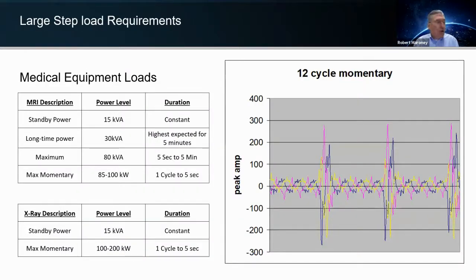So another type of load or requirement for a lot of people, and that is getting into medical equipment loads, is high nominal to peak requirements. Remember that 14 times inrush current we can provide? When you put a rotary UPS in, this capability, as you can see, we're going from 15 kVA, which would be about 12 kilowatts, up to 100 kilowatts in sub-cycle transients.